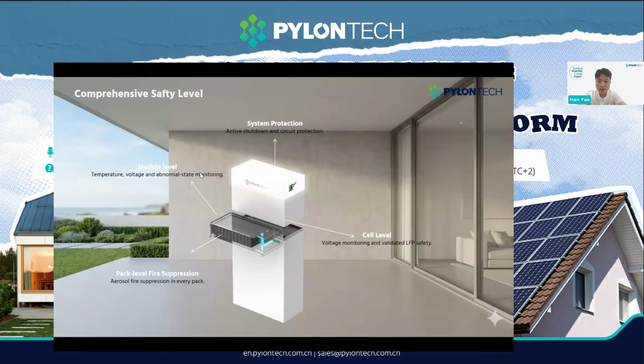And in this slide, please pay attention to our protection strategy. Safety is built in several levels. At the cell level, the system monitors voltage and uses proven LFP chemistry. At the module level, it checks temperature, voltage, and abnormal conditions. Each pack also includes aerosol fire suppression. At the system level, active shutdown and circuit protection provide another layer of control. Why use several layers? Because one safety action is never enough for energy storage. We all know about that. The complete design works together to detect problems early, control risk, and protect the full system.